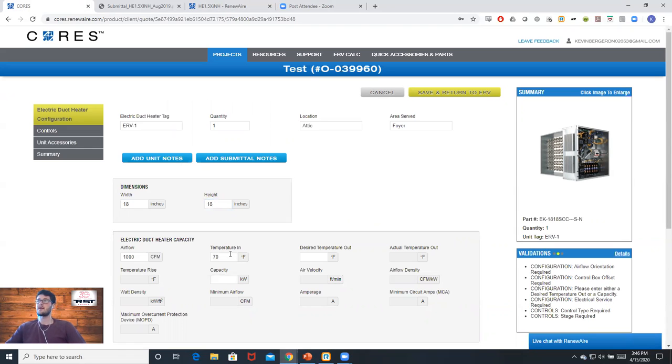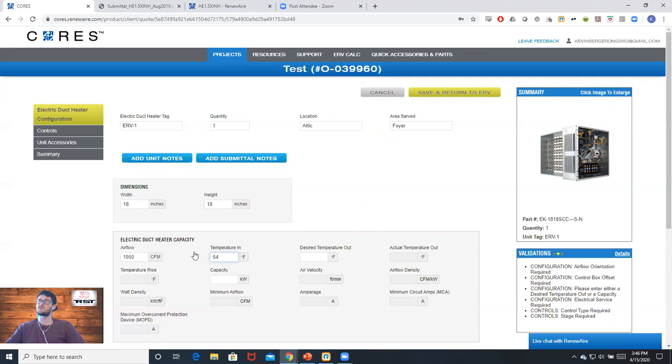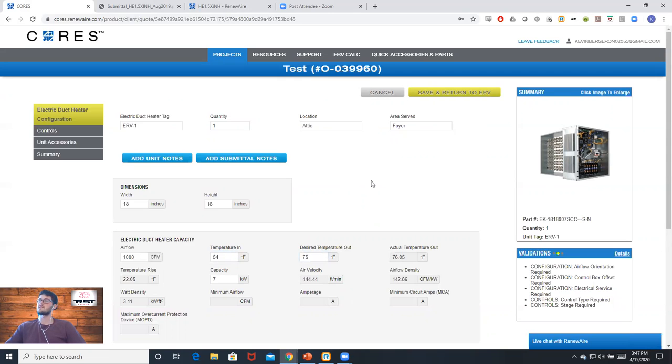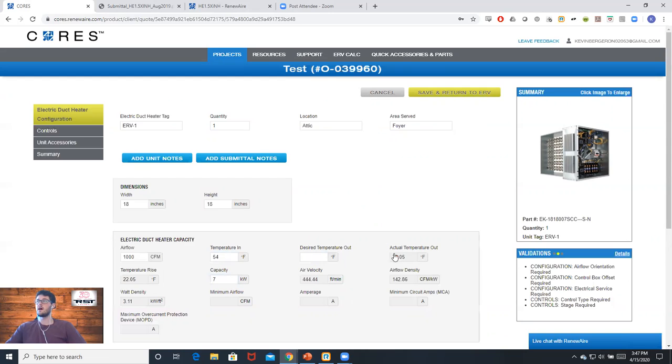Once we have that entered, we can type in our temperature in, which was 54 degrees, and our desired temperature out, which for this example I'll say 75. Once you click out of that, you'll see what our capacity needs to be to get that temperature rise, along with what the actual temperature out is if we were running it at full 7 kilowatts.